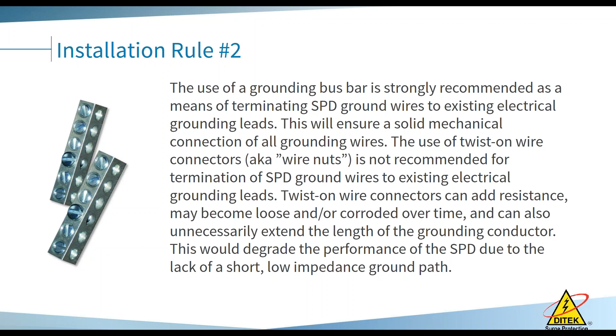Somebody comes by later. If it's internally in a breezeway fire alarm, somebody's moving a couch in there, and they bang that thing, the wire comes out of the wire nut, it's shot. Field-mounted boxes, guys mowing the lawn, hits into the box, bang, one of those wires comes out of the wire nut. We always recommend ground buses just for solid mechanical connections for that reason.